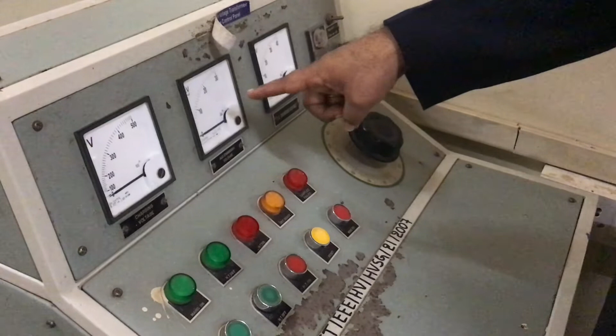Now we will see the practical case. Switch on the mains and switch on the HT. Since we are connected with HVAC, the voltage is varied. Slightly keep increasing the voltage. Right now it has reached 5 kV, 7 kV, 9 kV. At 9 kV it got breakdown, but we could not see the spark at the two spheres clearly, so now we will focus on the sphere.